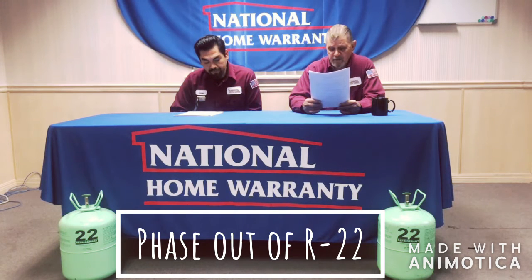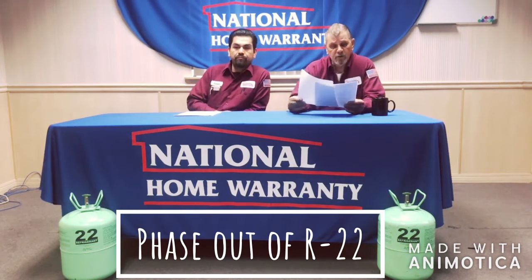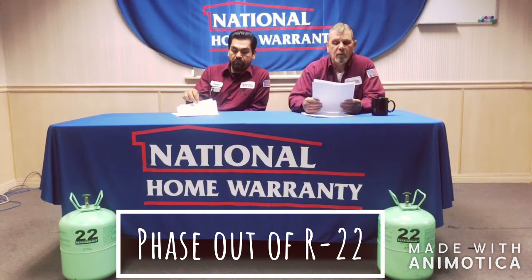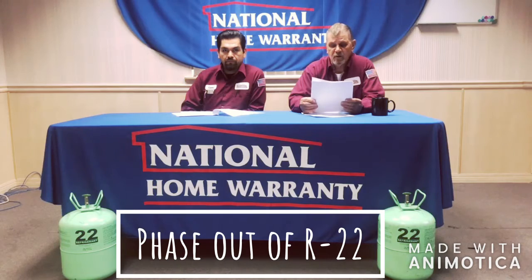When exactly did the phase out of R22 start happening? In approximately 1992, the EPA began the phase out of R22 due to the depletion of the ozone layer. In 2015, there was approximately a 90% reduction of R22. By next year, 2020, there will be a 99% near elimination of R22 production, and it will no longer be produced, imported, or sold in the USA. The cost of R22 refrigerant is approximately double the cost it was a decade ago.